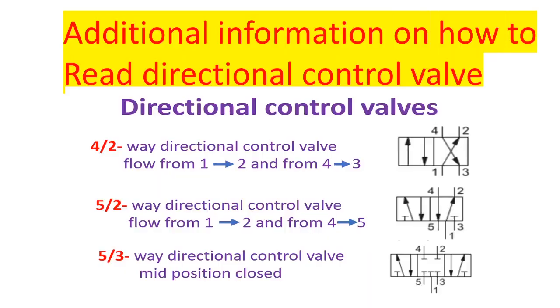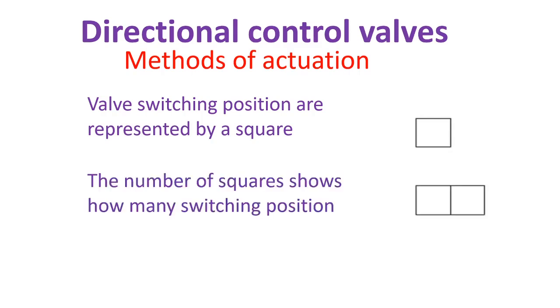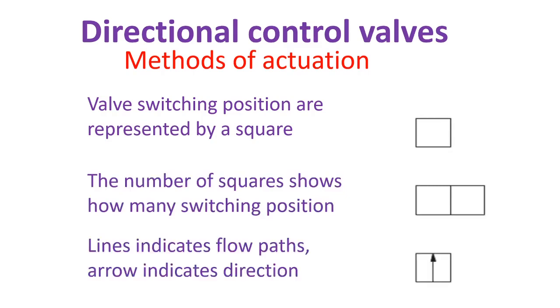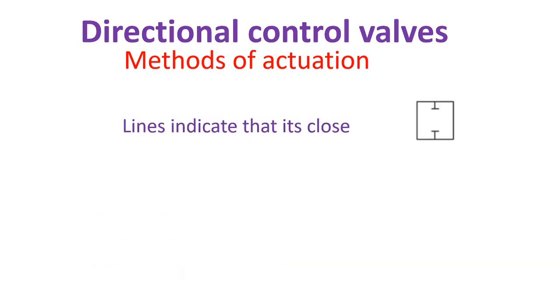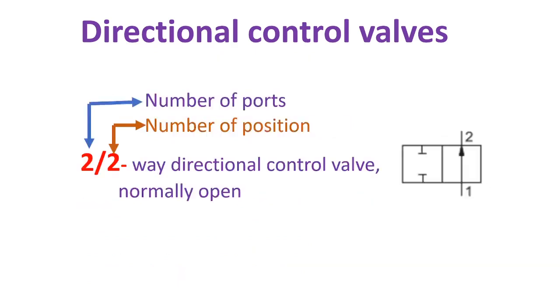Don't skip the video — we have additional information on how to read directional control valves. Valve switching positions are represented by a square; the number of squares shows how many switching positions there are. Lines indicate flow path, arrows indicate direction, and a line across indicates it is closed. Connections appear outside the box or valve. The first letter represents the number of ports, and the second letter represents the number of positions.